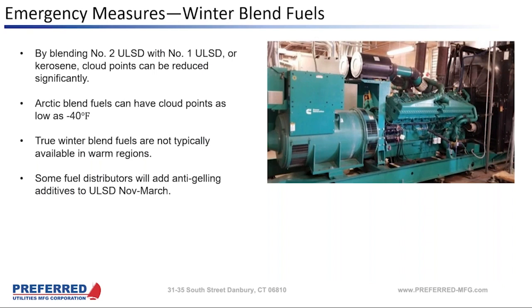So yeah, during 2021, I got a call from a plant that I actually helped get going on oil before the cold weather hit, because all the dual fuel plants in the DFW area were notified that on Saturday at noon they were going to have their natural gas cut off. They had to go to diesel. So I helped get their 2 water tube boilers going on diesel fuel. The next morning, I get a call from the plant manager, and he says, "I've only got like 18 hours of fuel left here."